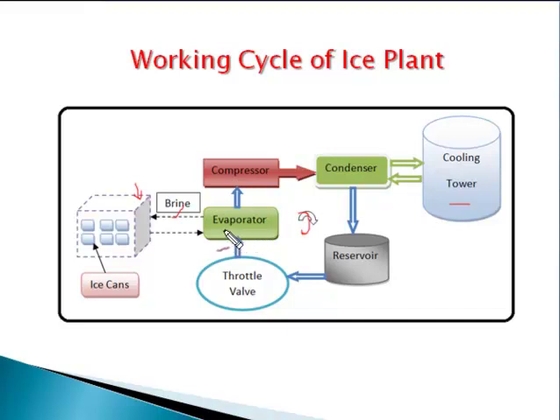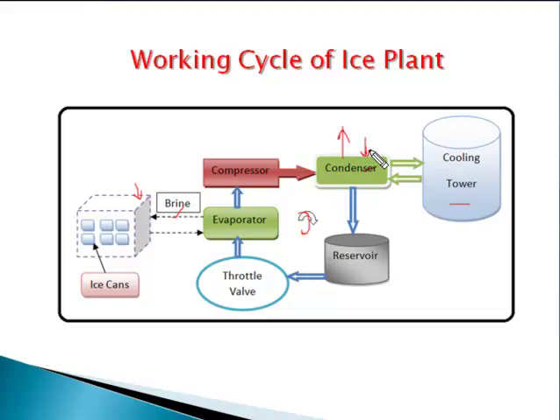The primary refrigerant absorbs heat in the evaporator from the brine solution. This refrigerant is then sent to the compressor, which compresses the refrigerant from low pressure to high pressure and sends it to the condenser, where heat extraction takes place. In the case of an ice plant, a water-cooled condenser is used because a larger amount of heat extraction is needed. The cooling medium from the cooling tower enters the condenser, and after absorbing heat, this water is sent back to the cooling tower.